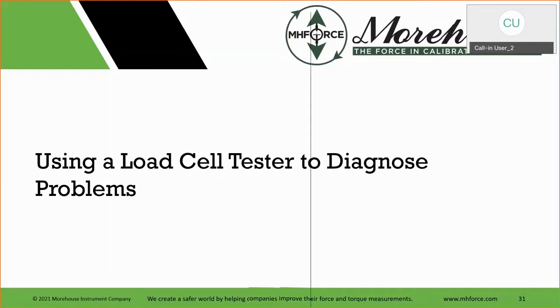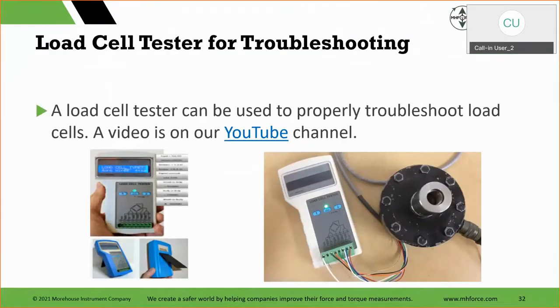That's not to say shipping, someone didn't drop it. Also, these load cells, the impact force on them. If somebody drops a load cell, like 3 feet with the smaller ones, that could completely shift. There's force equals mass times acceleration. That impact is quite severe. So like a 300-pound load cell, 500, 1,000. If it's dropped, if it's not packed properly, it can be destroyed in shipping, or can be destroyed by someone accidentally dropping it. Just something else.